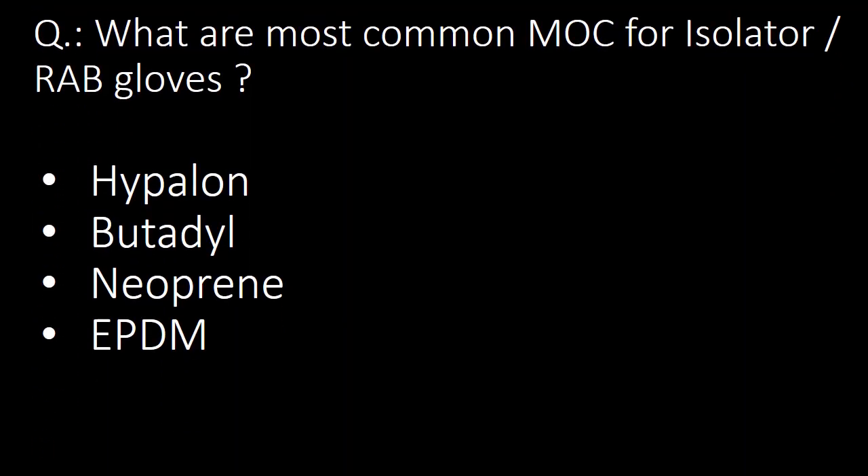What are the commonly used materials of construction (MOC) for Isolator or RAB Gloves? Hypalon, Butadyl, Neoprene, and EPDM are the commonly used materials for Isolator or RAB Gloves.